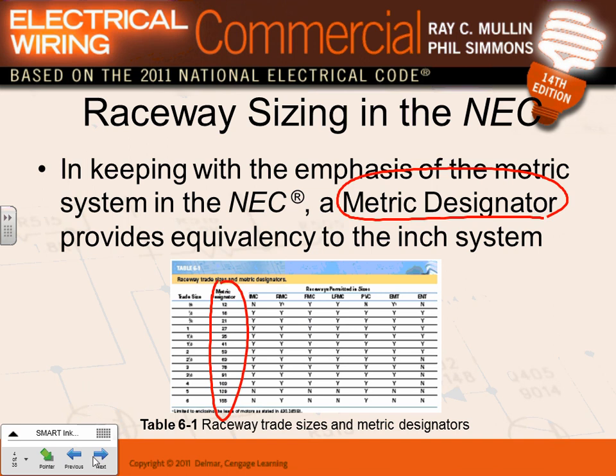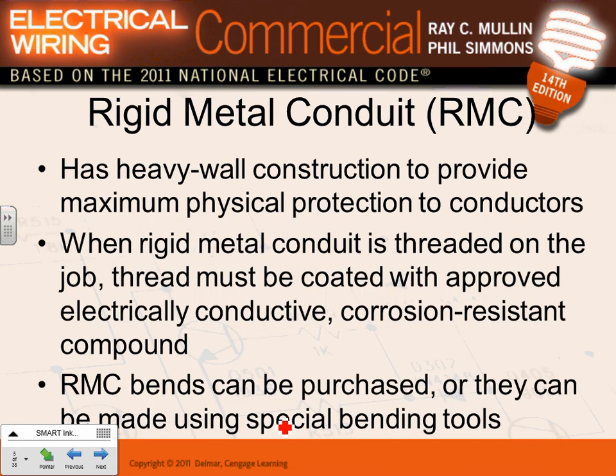Moving into rigid metal conduit - this is the worst conduit you're going to encounter. It's the hardest to work with, the hardest to bend, and it's threaded. Why would you use rigid metal conduit? Unless you have a need for severe physical protection for your conductors, or you're in a hazardous classified location - class one or class two - you would not use rigid metal conduit.